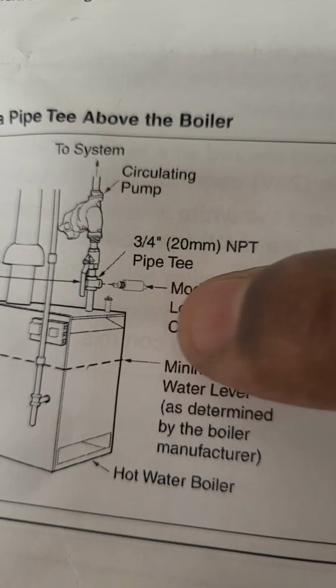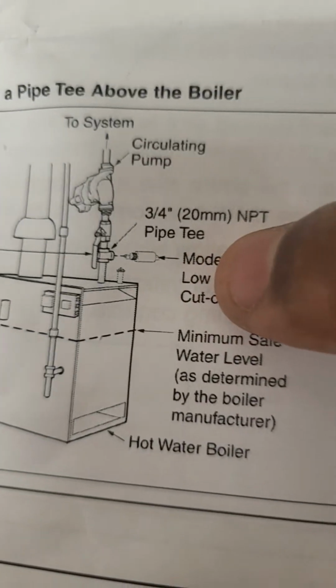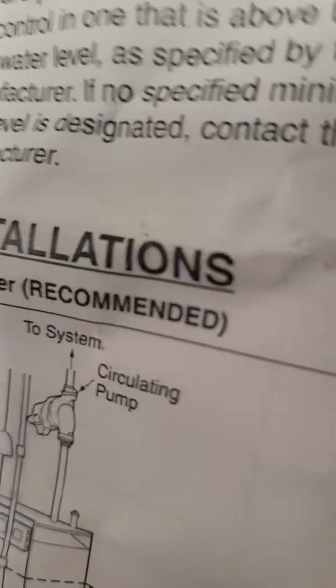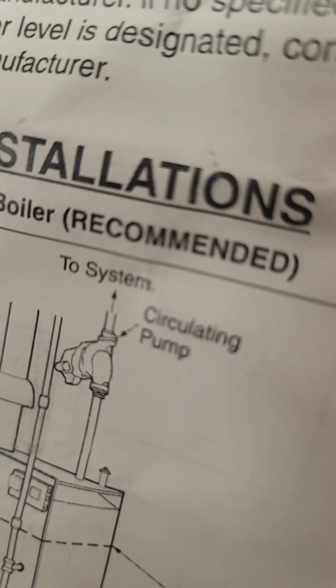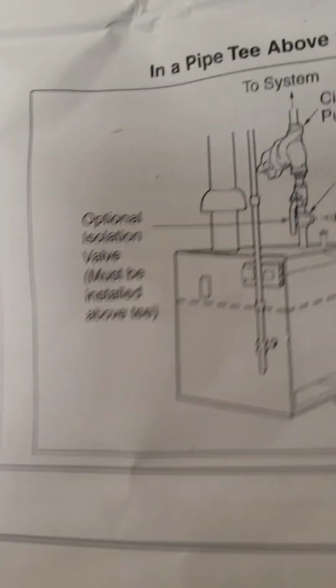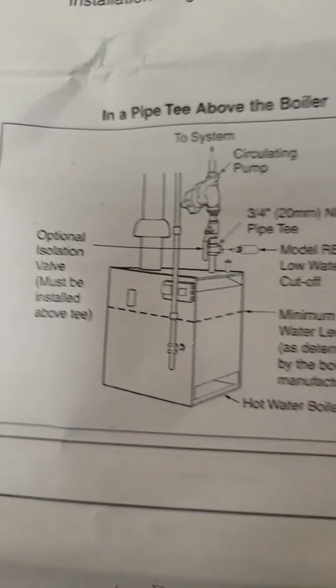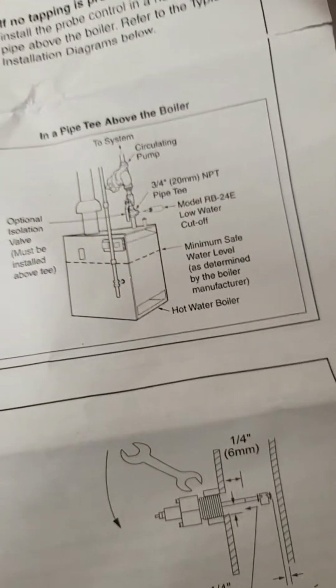But once again, guys, before you remove this low water cutoff, make sure the water is drained from the boiler. And if you have isolation valves, make sure they are closed. You don't want to be that slimy sleazeball who goes in there and assumes that just because you did this 50 times before, it's going to be the same thing. No, treat every system differently.